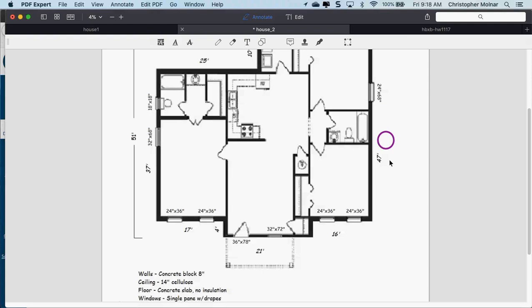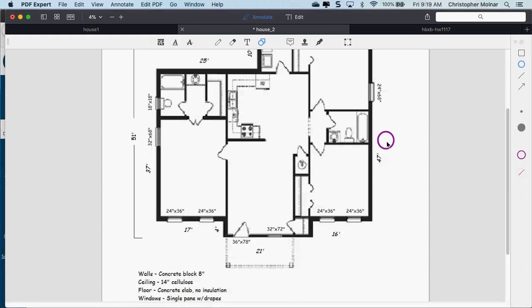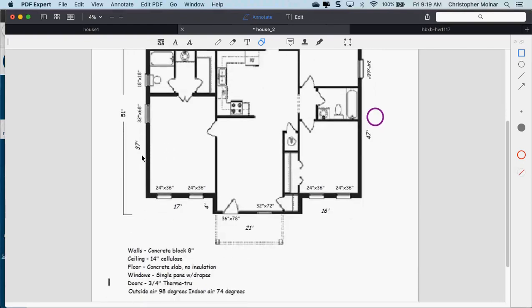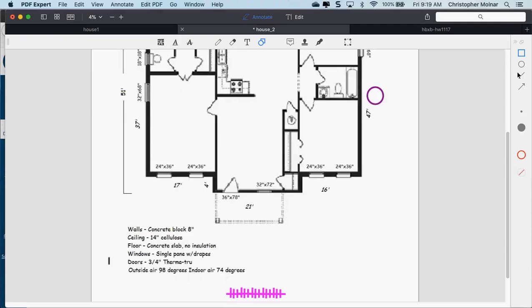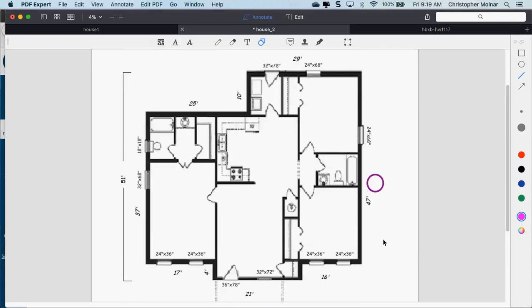People want things only doable with hot water but also want air conditioning. We basically have two options: run an air handler for cooling plus traditional baseboard around the outside of the house, or combine the hydronics into the forced air. We'd need a boiler. I try to place boilers on one side of the basement near an outside wall because I install high-efficiency, usually wall-mounted boilers — people like saving money.